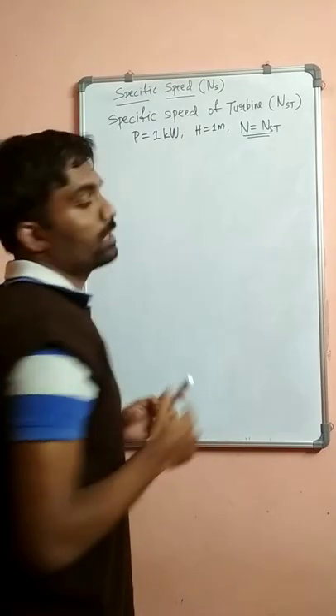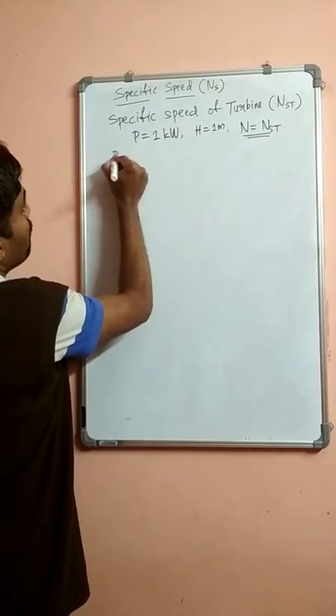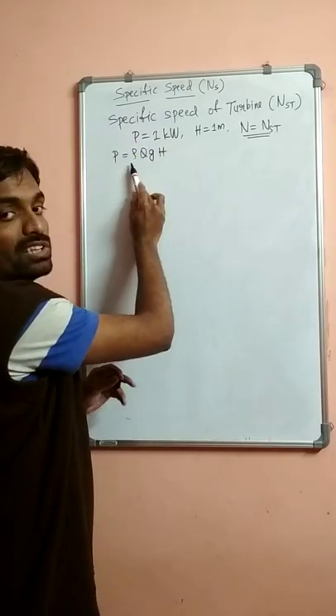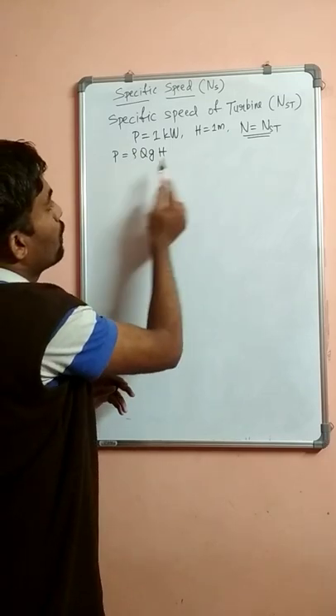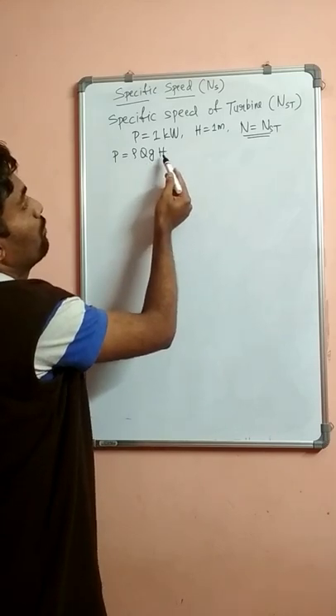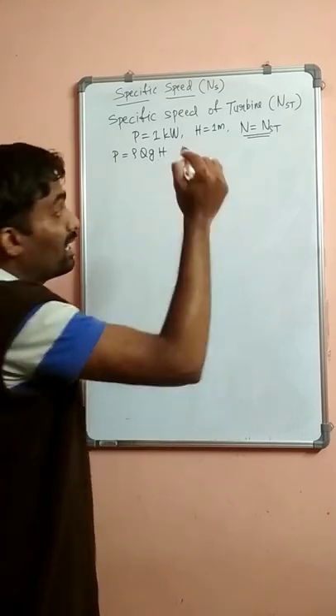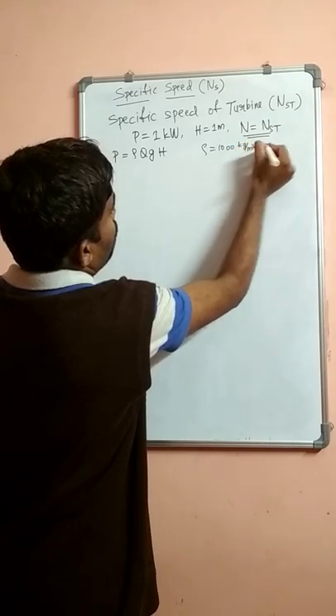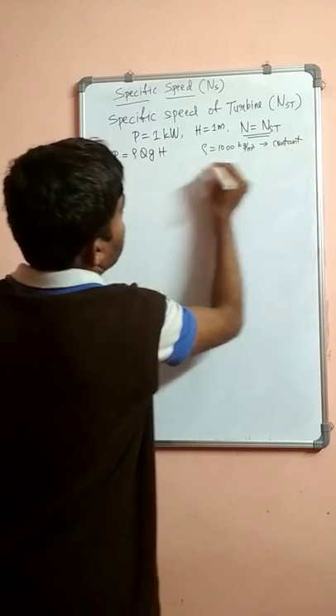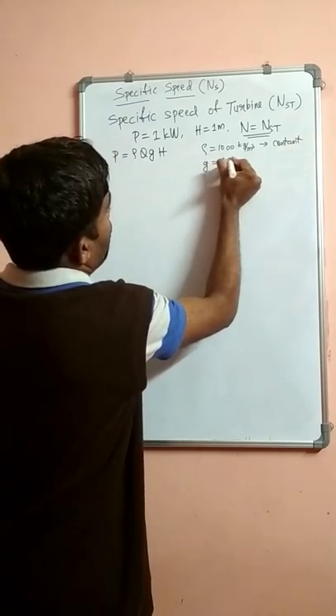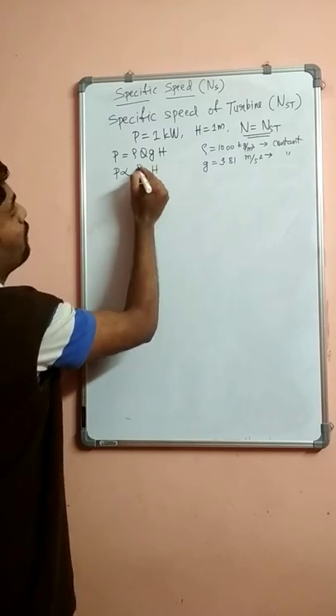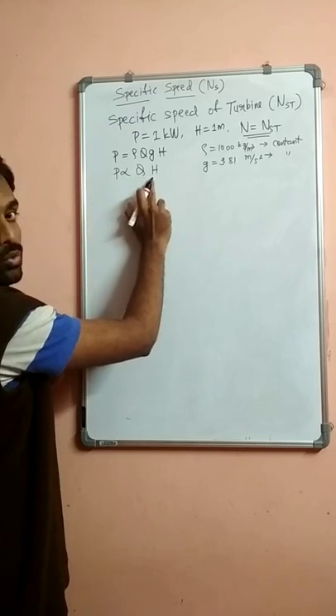Now let us try to obtain the expression for N-S-T. For this, we consider the basic equation P is equal to Rho Q G H, where P is power, Rho is density of the working fluid which is water with value 1000 kg per meter cube, Q is the discharge, G is 9.81 meter per second square, and H is the head available. Since Rho and G are constant values, we can modify the equation: P is proportional to Q into H.